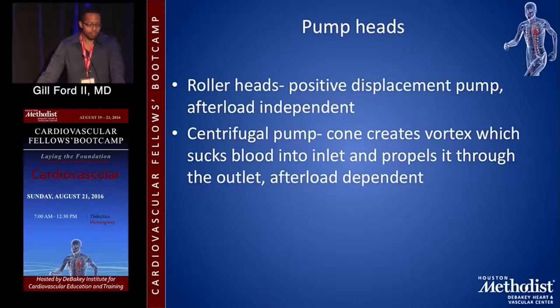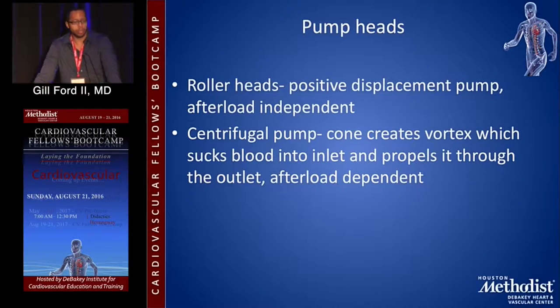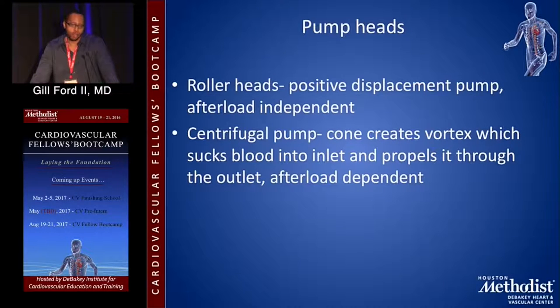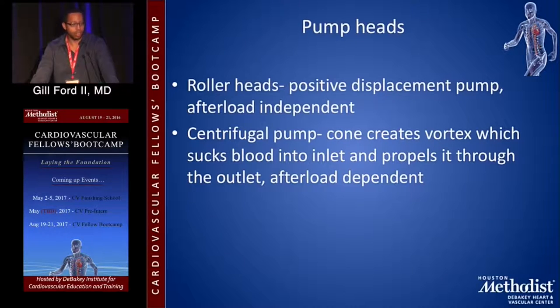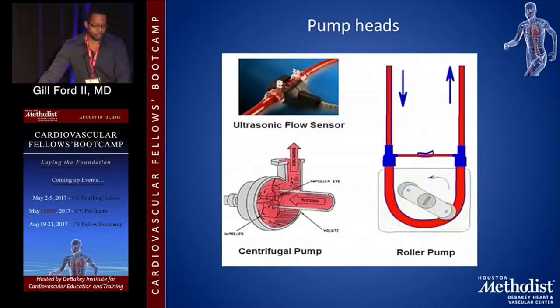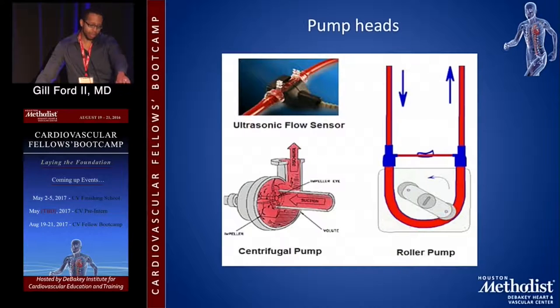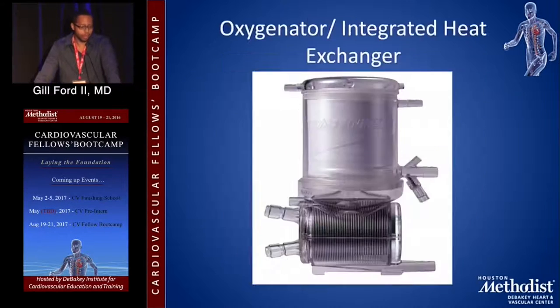With a centrifugal head, you have a pump that doesn't put as much shear pressure on your red cells. The centrifugal pump creates a vortex, spins, sucks in the blood, propels it forward, and sends it back to the patient. The only real downside is that over time the pump head can heat up and cause red cell damage. Other than that, the centrifugal head is the gold standard for cardiopulmonary bypass. You can see the inner workings of the centrifugal pump alongside a roller pump in these images.